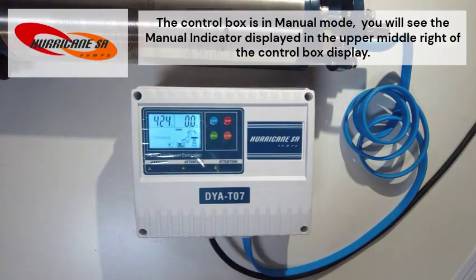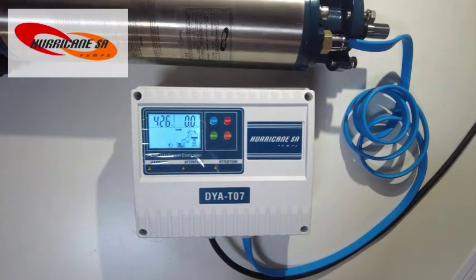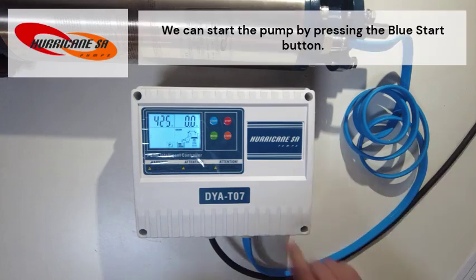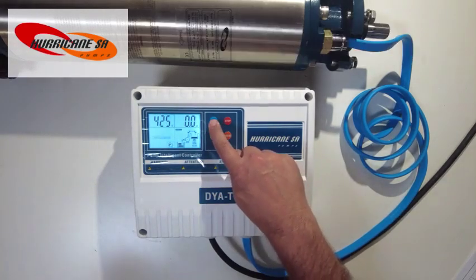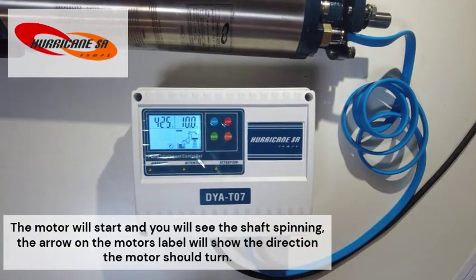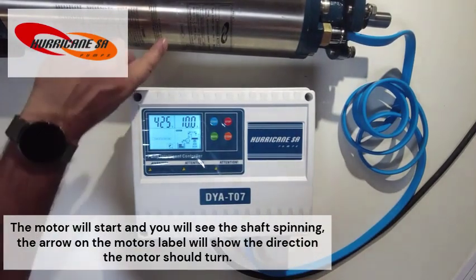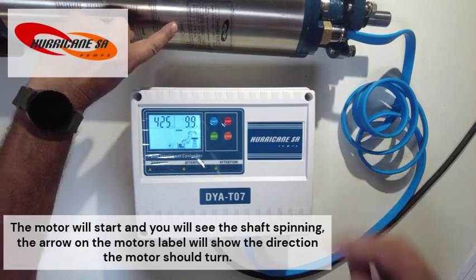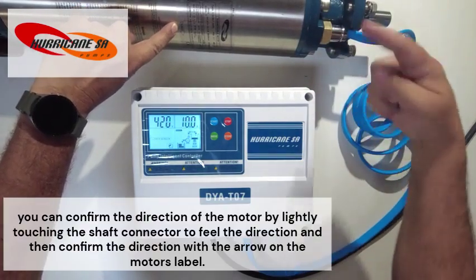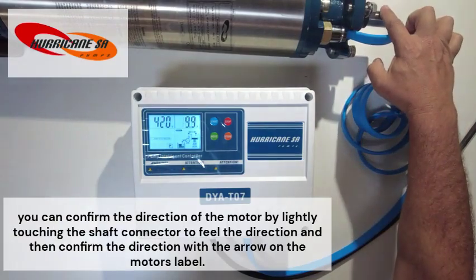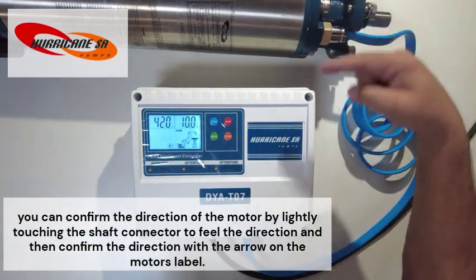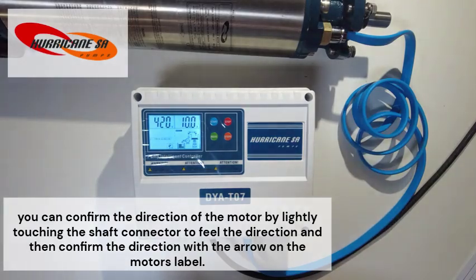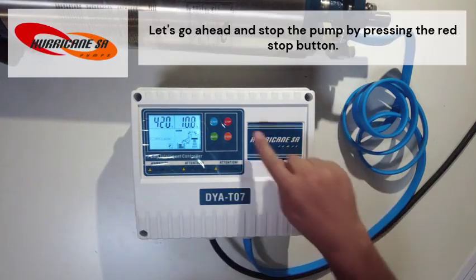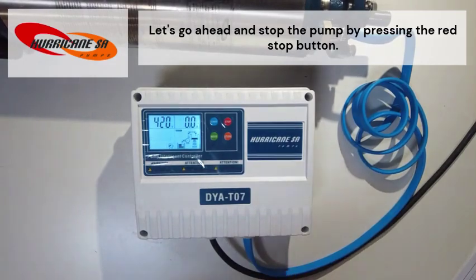The control box is in manual mode. You'll see the manual indicator displayed in the upper middle right of the control box display. We can start the pump by pressing the blue start button. The motor will start and you will see the shaft spinning. The arrow on the motor's label will show the direction the motor should turn. You can confirm the direction of the motor by lightly touching the shaft connector to feel the direction, and then confirm the direction with the arrow on the motor's label. Let's go ahead and stop the pump by pressing the red stop button.